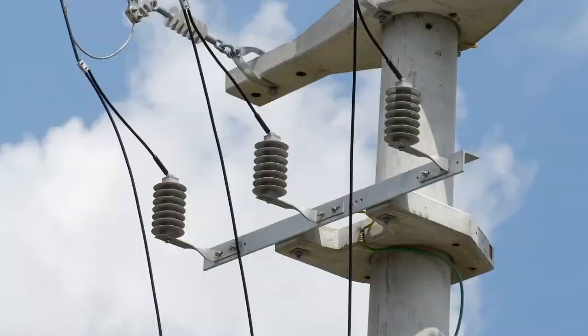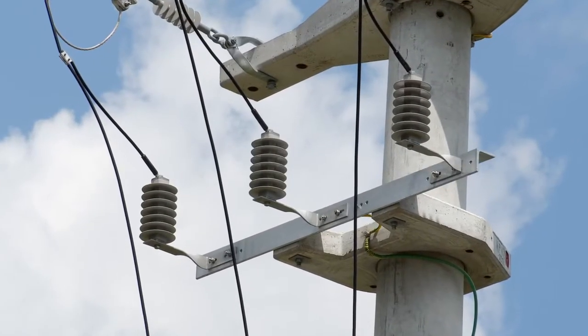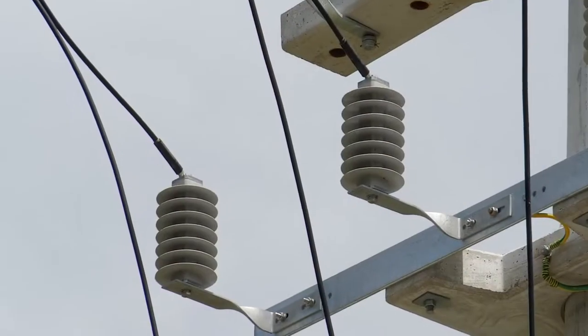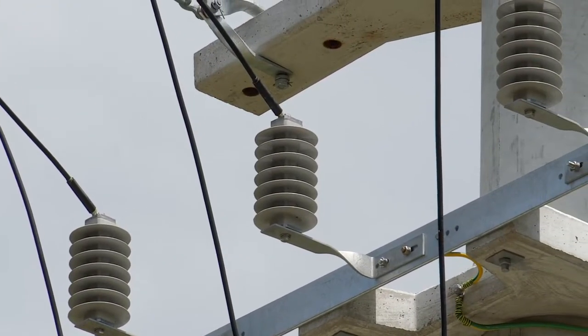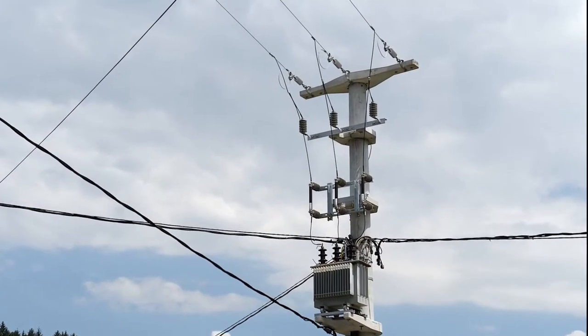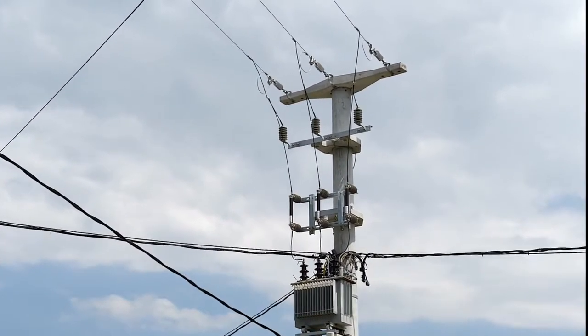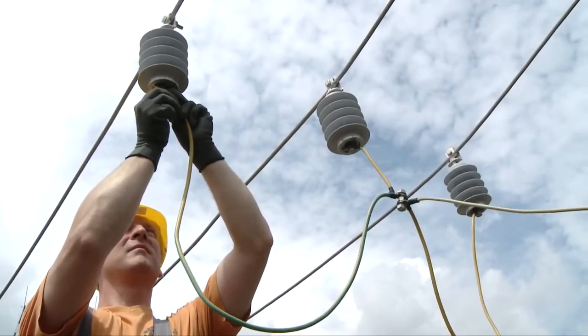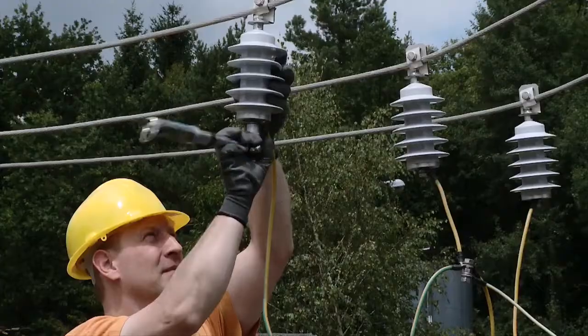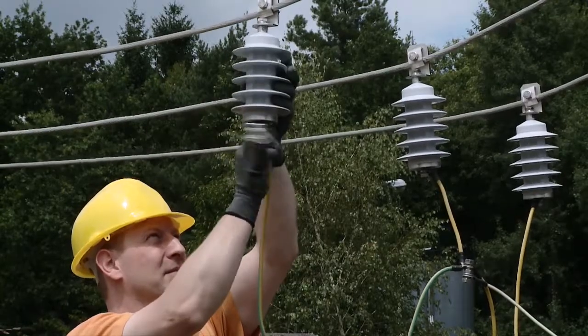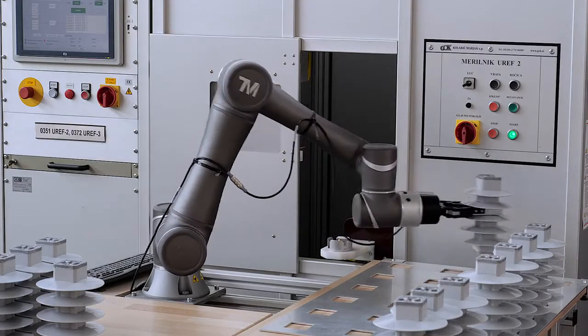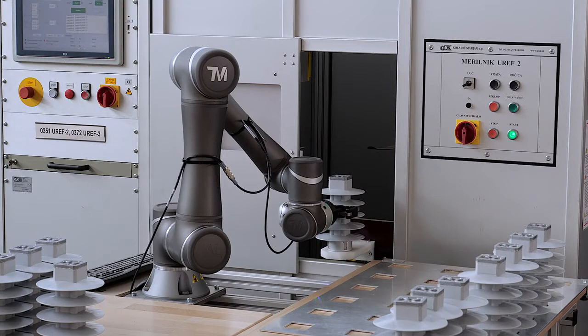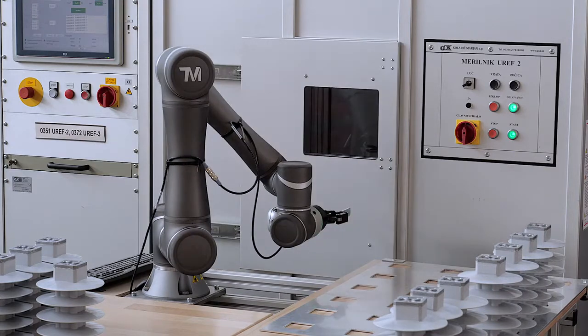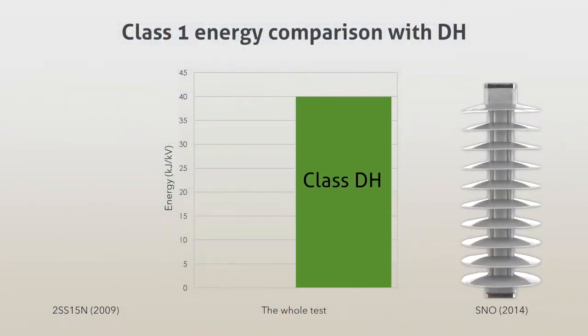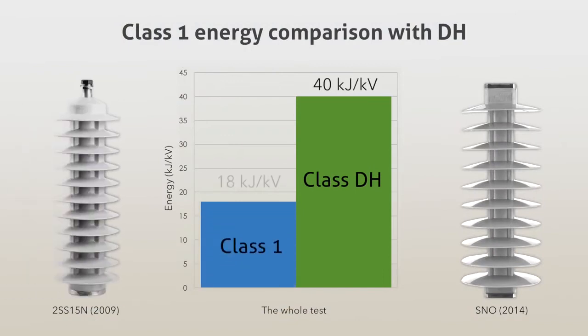Middle voltage zinc oxide surge arresters, which we have been producing for many years. Our devices intend to protect middle voltage power lines up to 44 kilovolts against direct lightning strikes. We produce Class 1 surge arresters according to a standard which was valid up to 2014. From 2014 on, we have also been producing Class DH surge arresters, which have 120% greater energy absorption than Class 1 surge arresters.